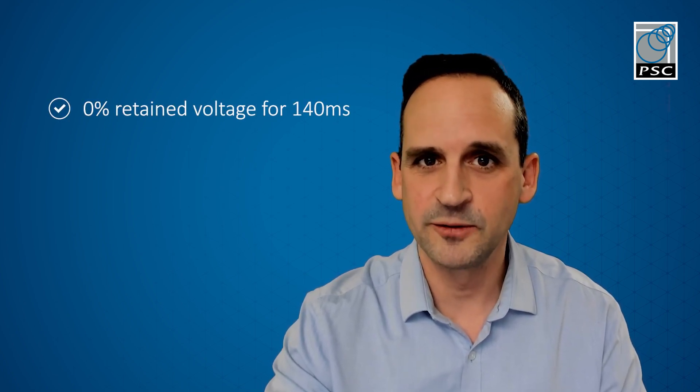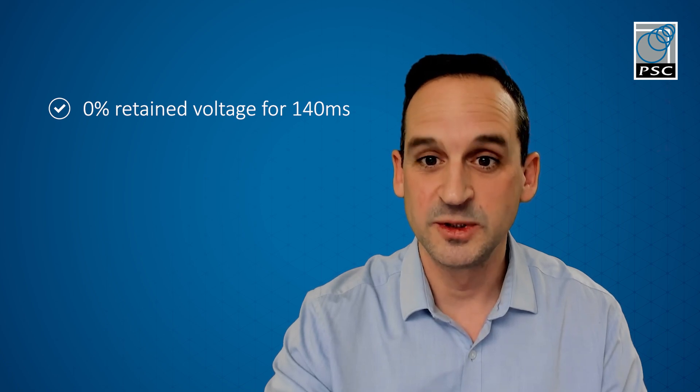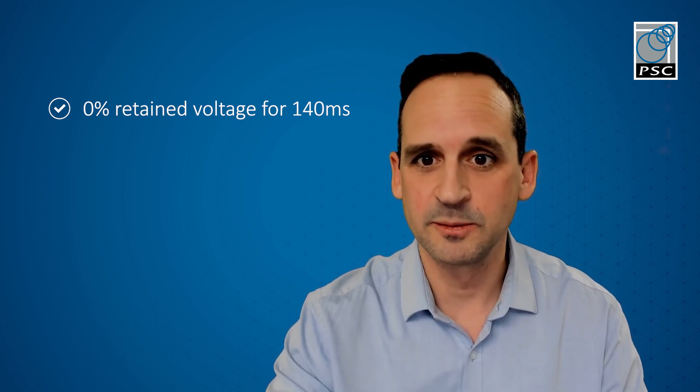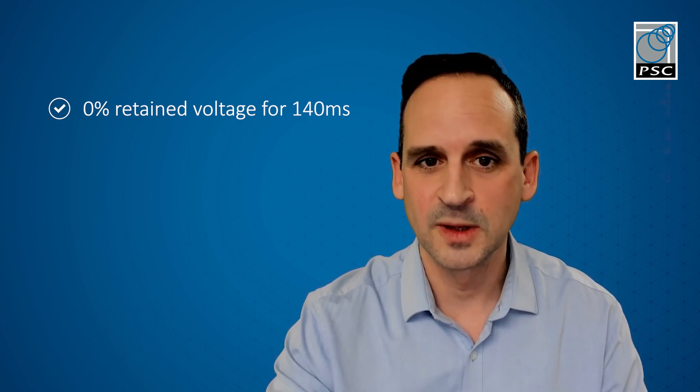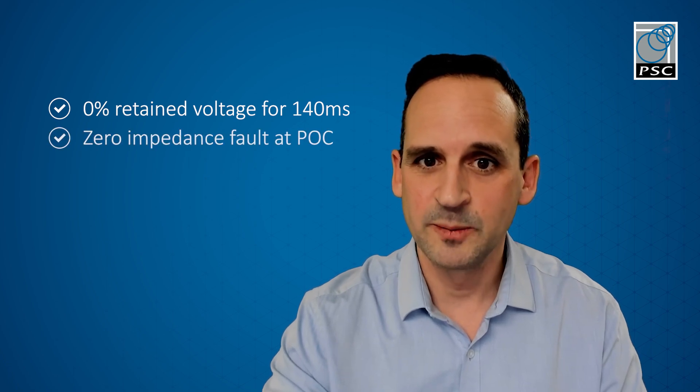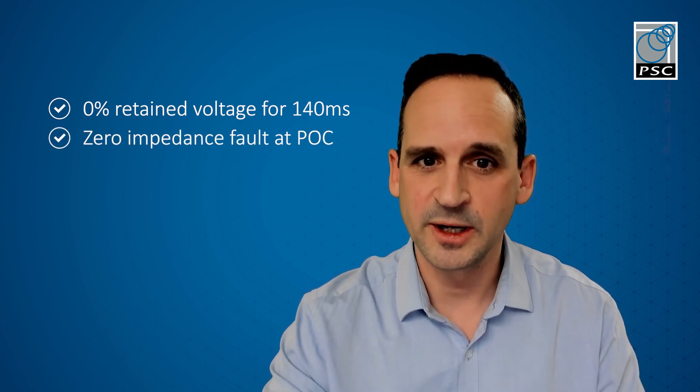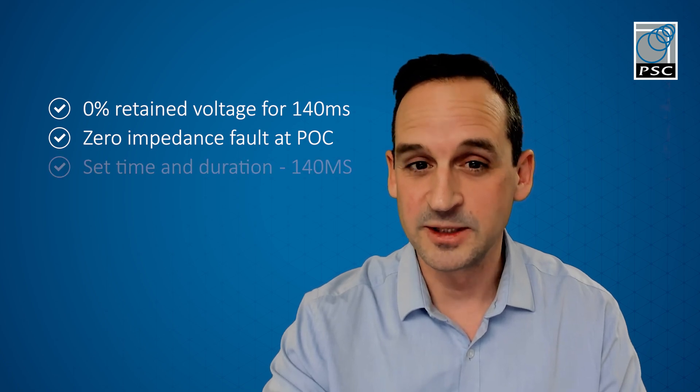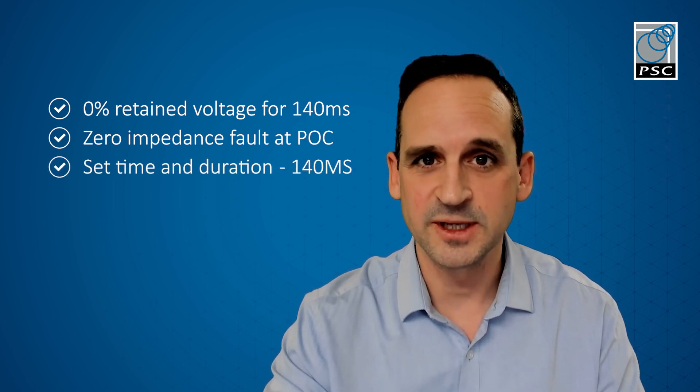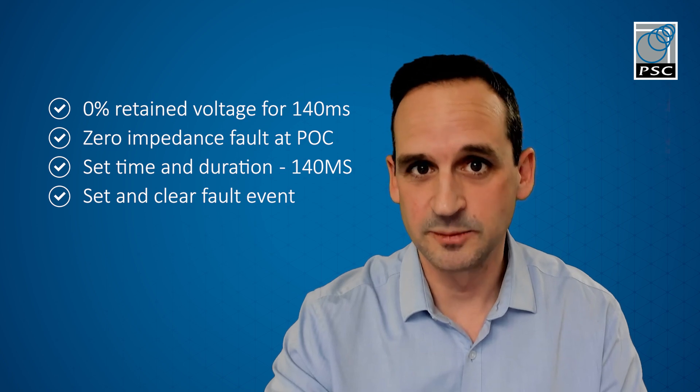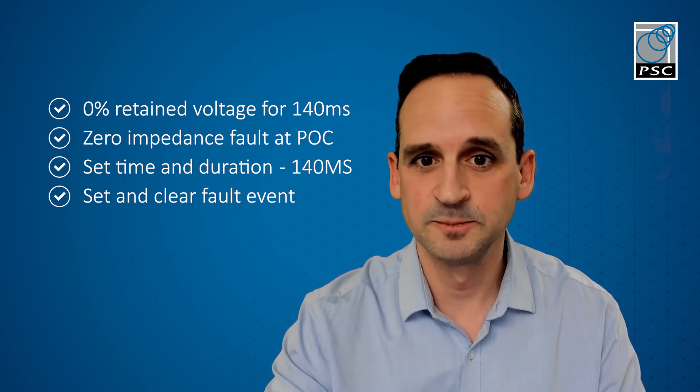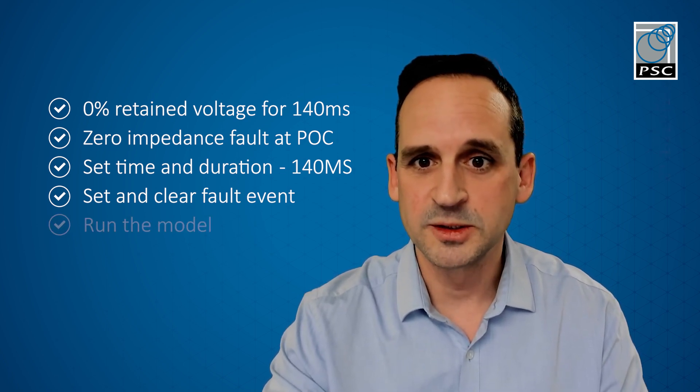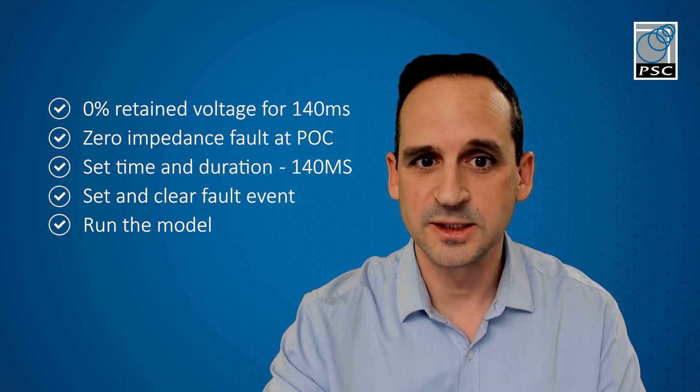For this example, we're going to use this model to demonstrate a voltage drop to 0% retained voltage for 140 milliseconds, just one of the studies that need to be done to meet grid code compliance. This means that a zero impedance fault will be applied at the grid connection point, causing the voltage at that point to drop to zero. This fault will remain there for 140 milliseconds. Then we clear the fault, representing the protection circuit breakers tripping, and continue to run the model up to 10 seconds.